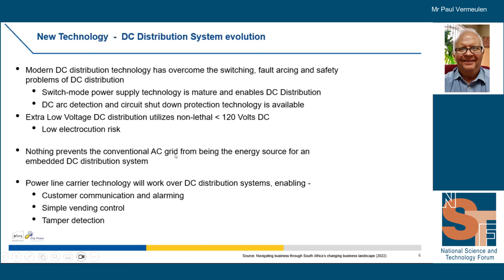Extra low voltage DC distribution, as it's defined by IEC, is less than 120 volts DC, and there's a low electrocution risk to it, so we can steer things towards non-lethal grids here. Nothing prevents the conventional AC grid also from being the energy source for an embedded DC distribution system. And also, of course, power line carrier technology, the communications, works over DC distribution systems as well, enabling things like alarms and simple vending and tamper detection as well. New tech, the clean and cheap new sources of energy.